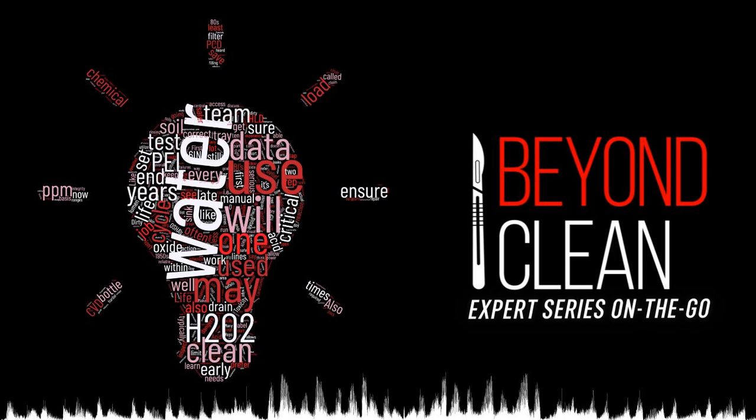The cleaning issues to be aware of: instruments can only begin to be considered clean if they are completely submerged in the ultrasonic bath. If not, the exposed portions of instruments will allow foreign matter to dry or biofilm to form. Make absolutely sure that the detergent is being dispensed into your machine properly. Given the fact that your dishwasher doesn't reuse the same water, consider draining the water after each use. Refer to AAMI ST-79, 2017.